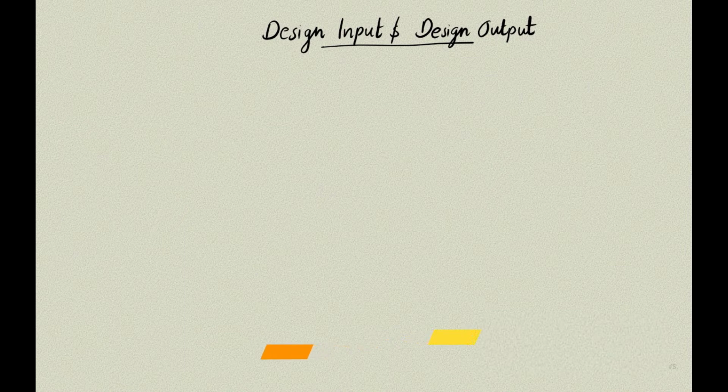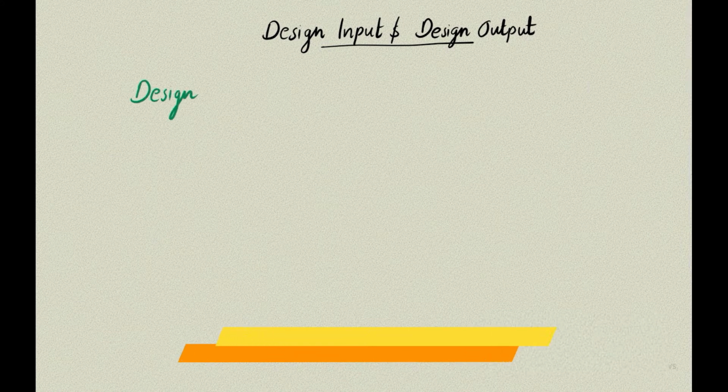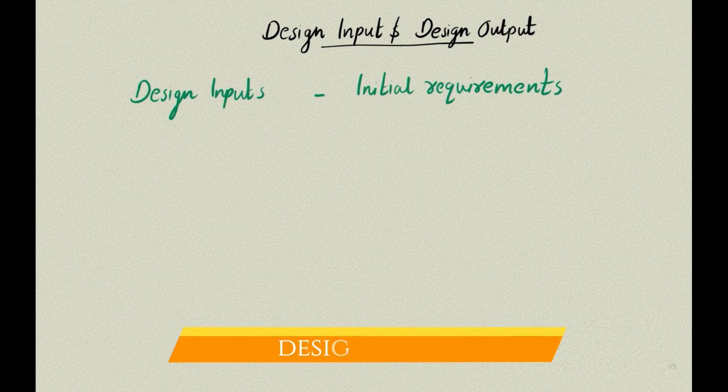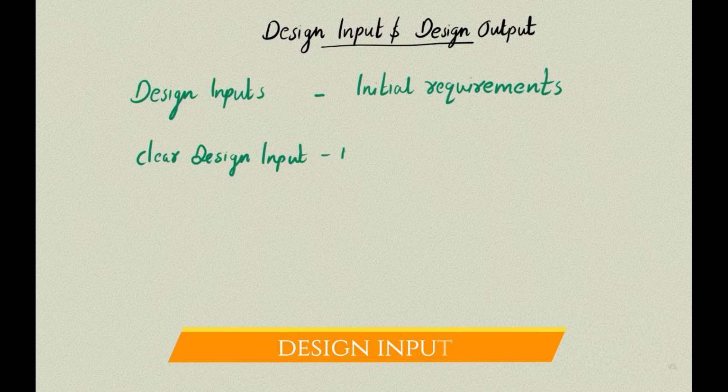So design inputs are typically the initial requirements that describe the medical device to be produced. The design inputs are the foundation of the medical device because the device is only effective when the design inputs are met during the development process. So a well-established design input can make the rest of the design development process easier because it's the driving factor, and everything is based on the design input, and the product is going to be verified with respect to the design input at the end.